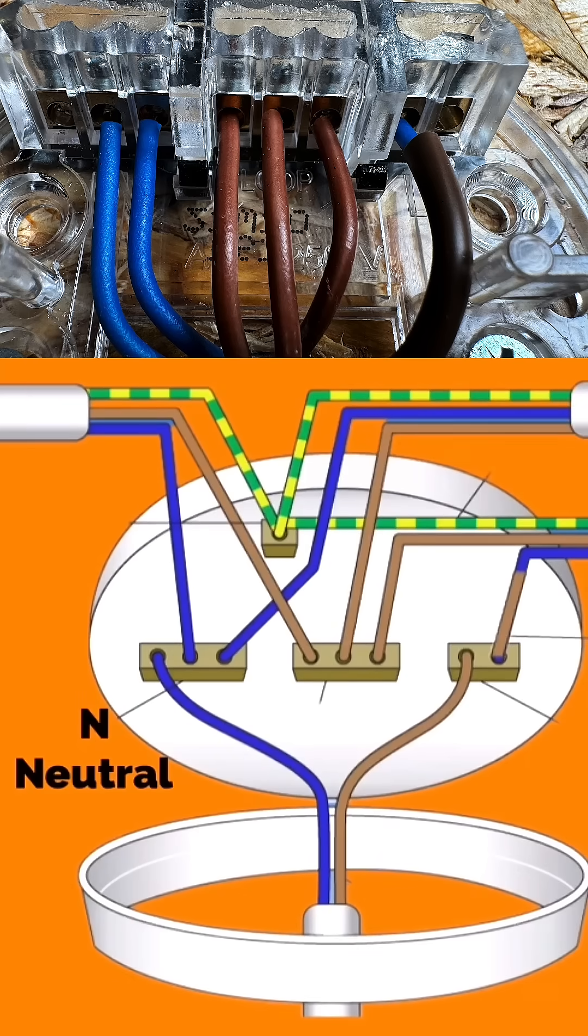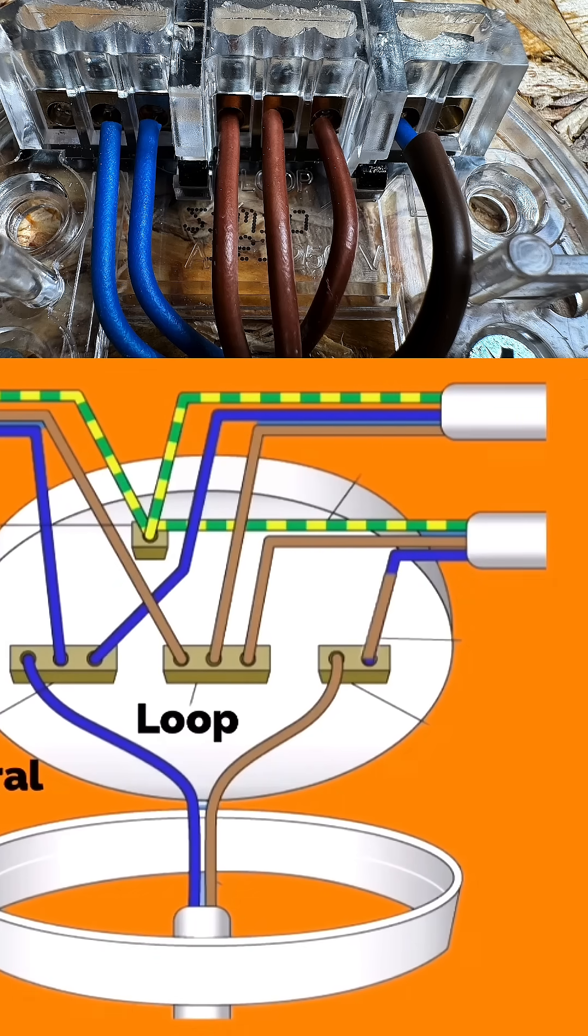The centre block of three is identified with the word loop and has the permanent line connections coming in and out of it. The far right-hand side is usually identified with the letter L, but is actually a switching line conductor that can give you control over the lamp by turning it on and off.